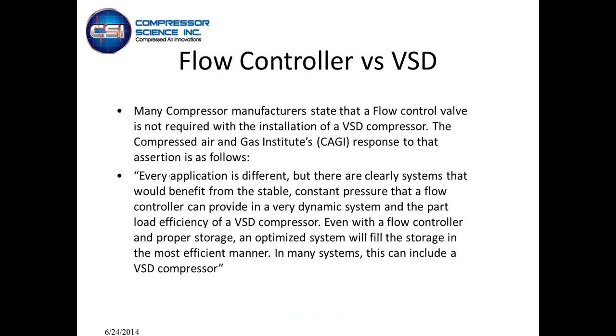Again, a lot of manufacturers say you don't need a flow controller if you have a VFD, because the VFD will trim the plant up and down, similar to a modulation valve on the flow controller. But what CAGI says is basically what I'm saying: every application is different. There are clearly systems that would benefit from the stable, constant pressure that a flow controller can provide in a very dynamic system, and part of that is the load efficiency of a VFD compressor. Even with a flow controller and proper storage, an optimized system will fill the storage in the most efficient manner. In many systems, it can include a VFD compressor.